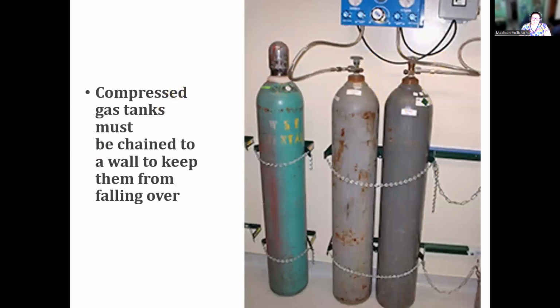Then we have compressed gas tanks. So things like oxygen, nitrous oxide, most of the time it's going to be oxygen. They have to be chained to a wall to keep them from falling over. These guys have so much pressure in them. So think about your average tire is about 35 psi or pounds per square inch. These guys will come to us with over 2,000 pounds per square inch. If you've never seen Mythbusters, they did an experiment on how strong these torpedoes can be, and they torpedo through brick walls. They're going to torpedo through your legs. We need to be careful with them.